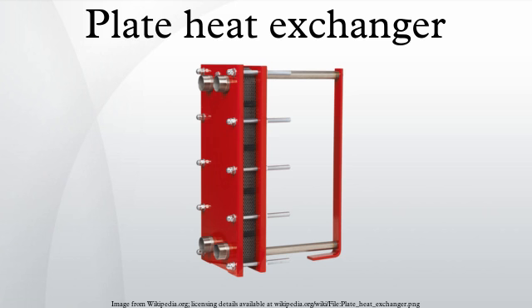A high degree of turbulence can be obtained at low flow rates and a high heat transfer coefficient can then be achieved. As compared to shell and tube heat exchangers, the temperature approach in a plate heat exchanger may be as low as 1 degree Celsius, whereas shell and tube heat exchangers require an approach of 5 degrees Celsius or more. For the same amount of heat exchanged, the size of the plate heat exchanger is smaller, because of the large heat transfer area afforded by the plates. Increase and reduction of the heat transfer area is simple in a plate heat exchanger, through the addition or removal of plates from the stack.